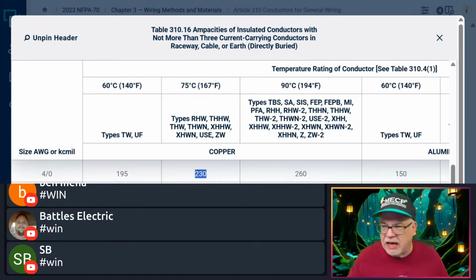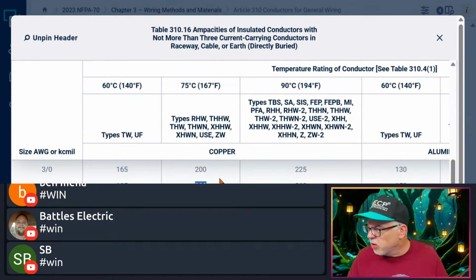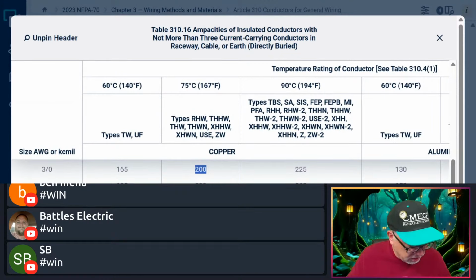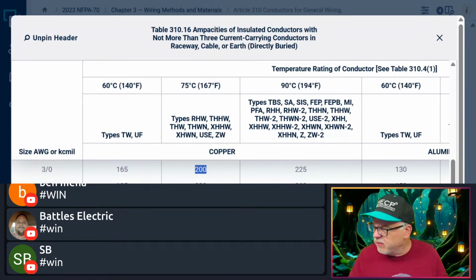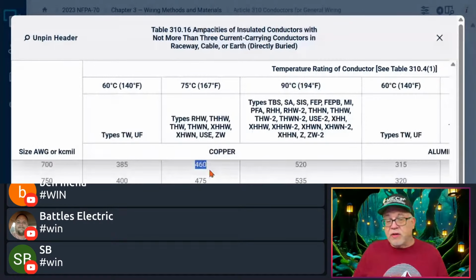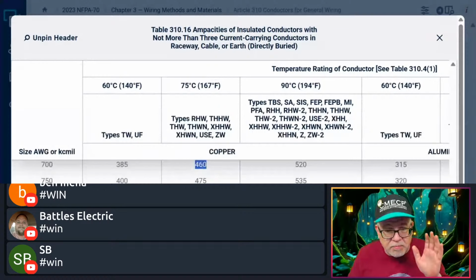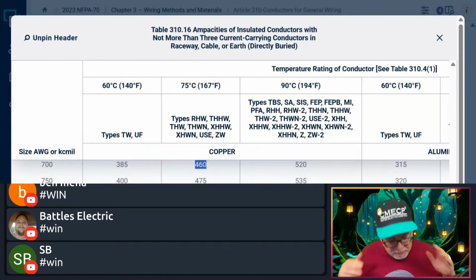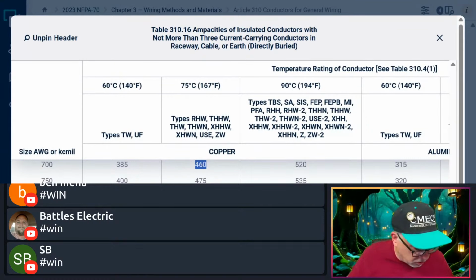The next was 4 sets of 3-aught. All right, so 3-aught right here is good for 200 amps. So it was 4 sets of 200. So 200 times 4, we know what that is. That's 800, not 1200. So it's not going to be 4 sets of 3-aught. And the last one we had to deal with was 700. And 700 is rated 460, and it says it was 2 sets of 700. I'm not going to try to run that anyway, I would not do that one, but for your example, 460 since it's 2 sets. 460 times 2 is 920.